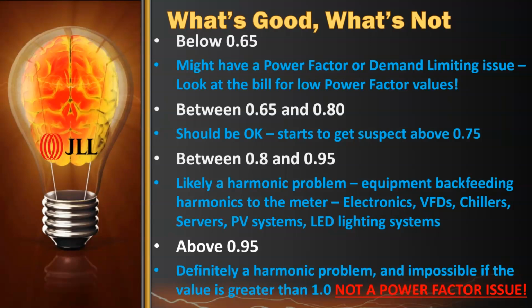So below 0.65, you might have a power factor problem or maybe a demand limiting issue. I want to look for low power factor values. Between 0.65 and 0.8, it should be okay, but when it gets above 0.75, I get itchy and I start to shuffle around my seat a little bit. And between 0.8 and 0.95, you likely have a harmonic problem. Definitely when you get up above 0.9, there's a harmonic issue in the building somewhere.